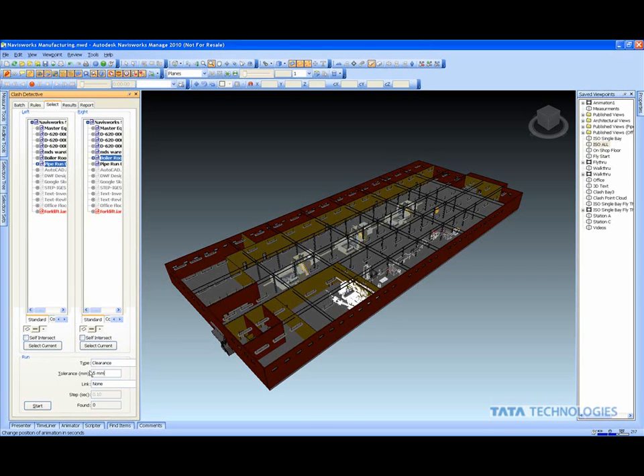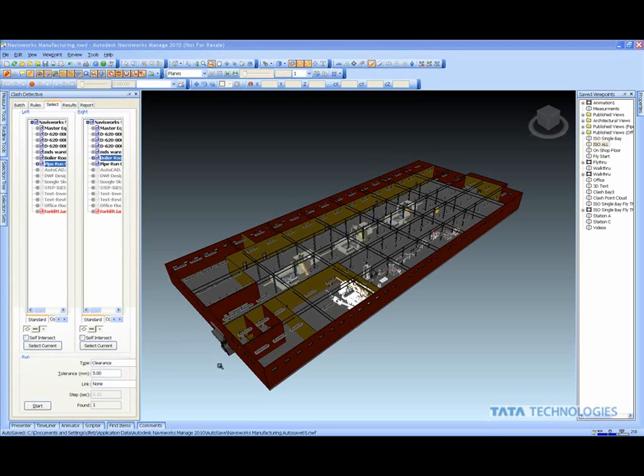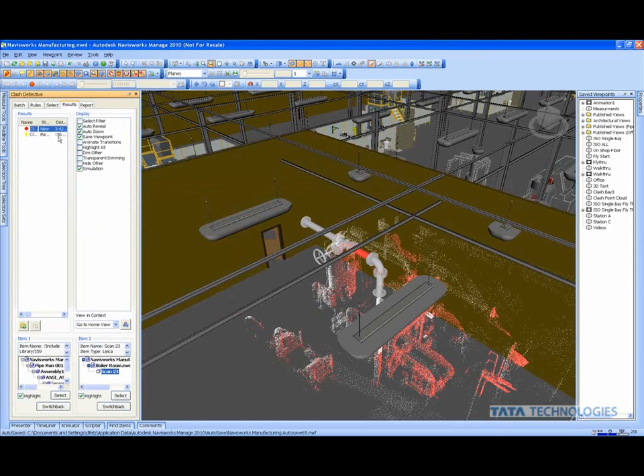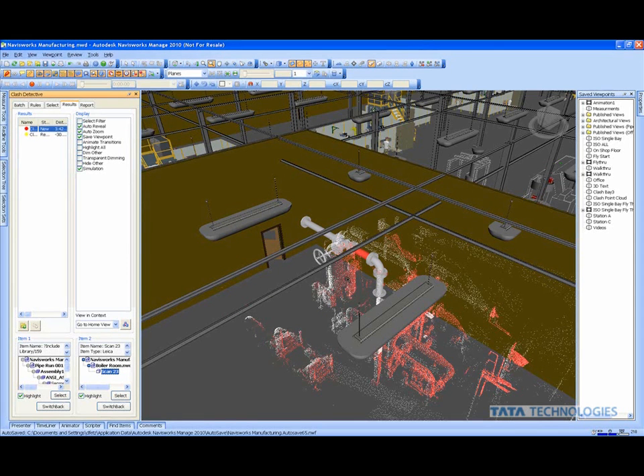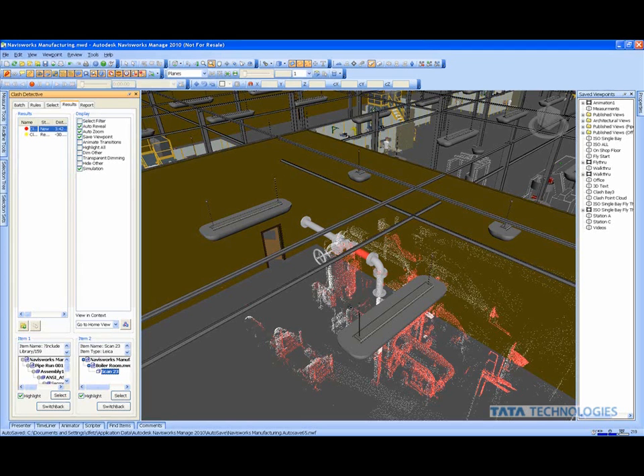This time, it's not all about 3D data—it's about utilizing that point cloud data. Navisworks is done. I'm in my boiler room and I can see that even with this point cloud data, with the rules I've set up, I may have some problems. We're really going to have to take a look at maybe some of the maintenance items, the routing of the pipes to verify and clean up this area to ensure we have proper clearances and prevent any unforeseen dangers down the road.